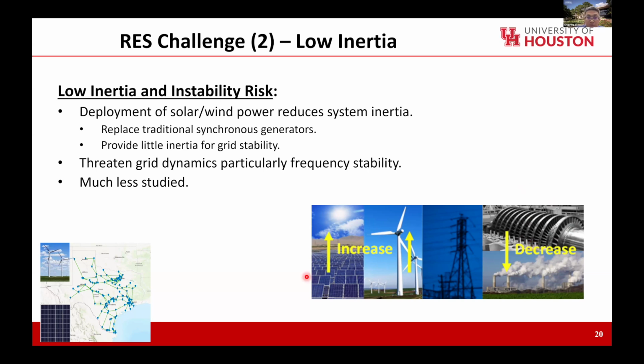But because we have much more solar and wind power, the traditional generators are used less. Some of them are retiring. Solar has no moving parts, so no synchronous inertia. Wind turbines do have rotating turbines, but they are much lighter compared to traditional generators, so they also don't provide much inertia. And inertia is super important for grid frequency stability. If the system is transitioning to a low inertia, weak system, we may have some dynamic issues, particularly frequency stability issues.